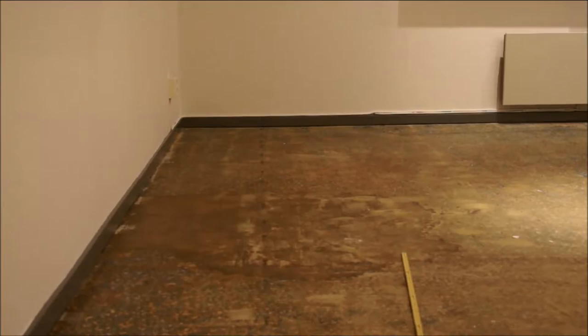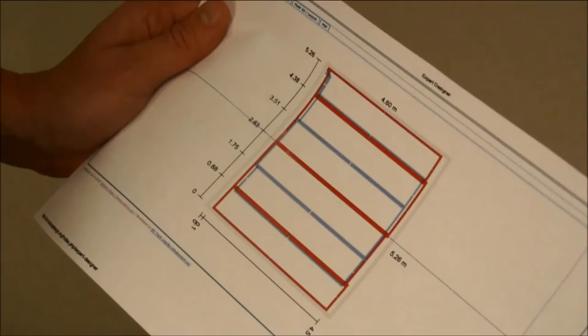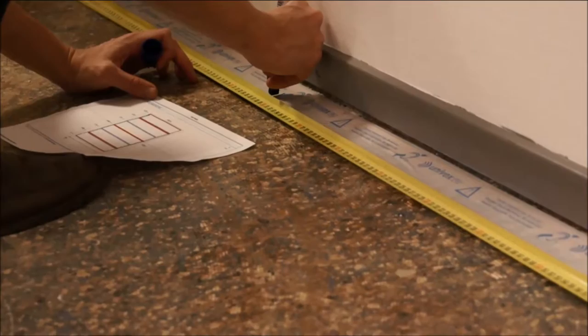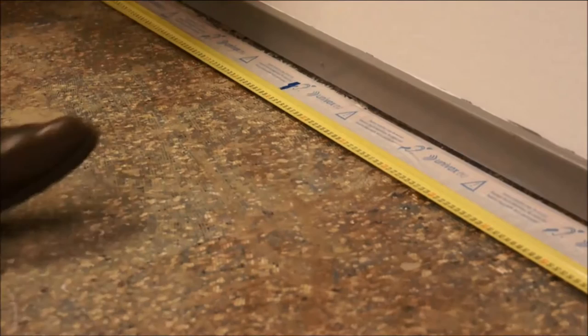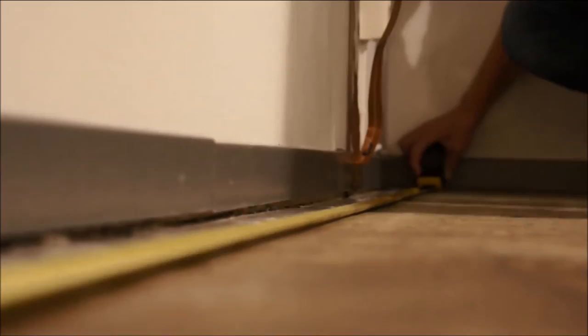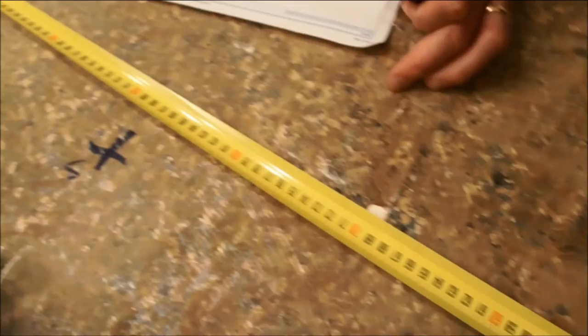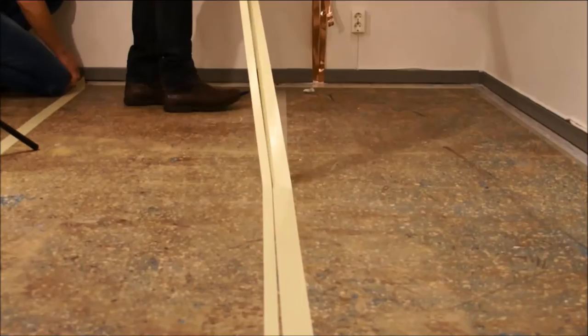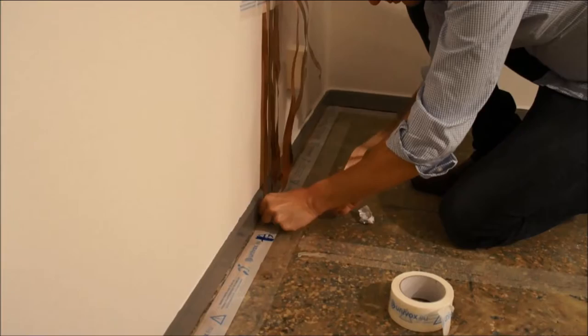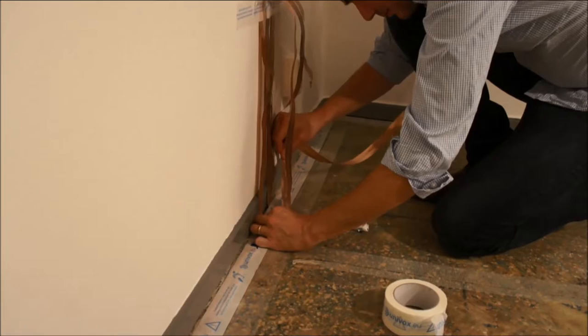Time for installation. First we mark on the floor where the cable will cross. We at Univox recommend double adhesive tape to tape down the copper wire to the floor. There are other methods and it is up to the installer to do as he or she feels comfortable. We recommend a 10 to 20 cm distance between the outer perimeter and the wall. This is to give the carpet installers room and avoid that the loop cable is accidentally cut.